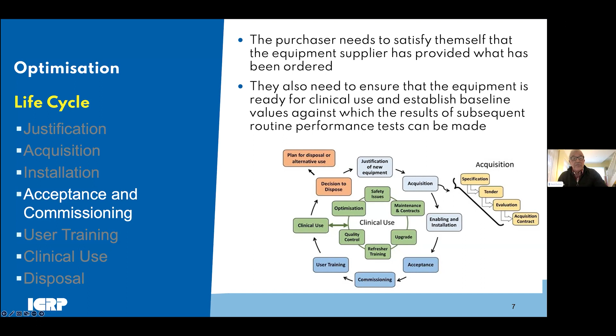And before the equipment can be used, as Colin pointed out, users need to be trained. Pretty obvious. User training is obviously of paramount importance, and a chapter of the report is devoted to it. But some of the main points discussed are: user training is critical for safe, optimized use of any imaging equipment. Initial user training should ideally be provided by the representative of the installer and the manufacturer following acceptance, and before the equipment itself is put into clinical use. And it's quite likely that not all end users of the equipment will be able to receive the initial training, since it should also be given to anyone who's required to use it after it's put in. Consequently, there need to be arrangements in place to ensure that training can be delivered by an agreed cascade process. And Kimberly is going to discuss this in more detail, as Colin has said, tomorrow.